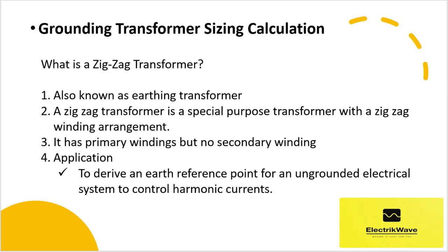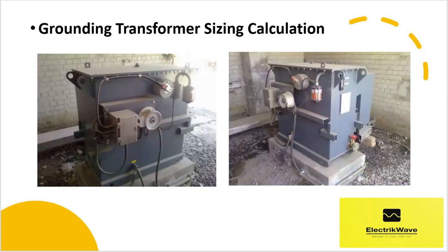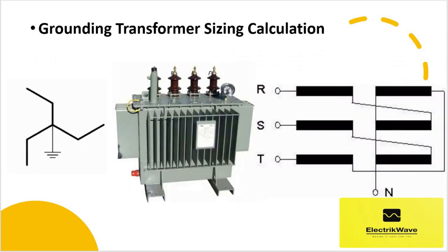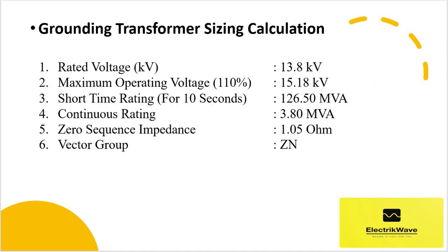A zigzag grounding transformer is used to derive an earth reference point for an ungrounded electrical system and to control harmonic currents. This is a photograph of the grounding transformer, and next is the pictorial representation of the grounding transformer — the MV side connection is through air bushings.